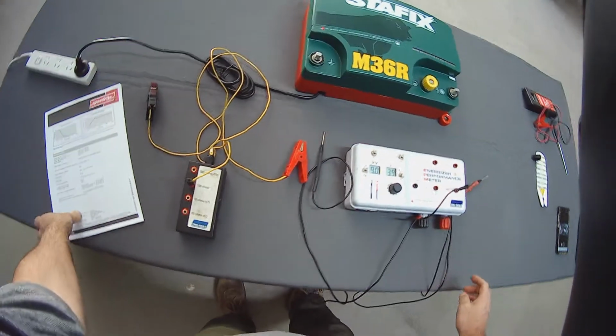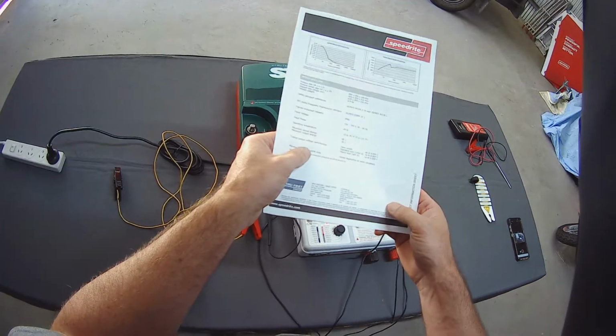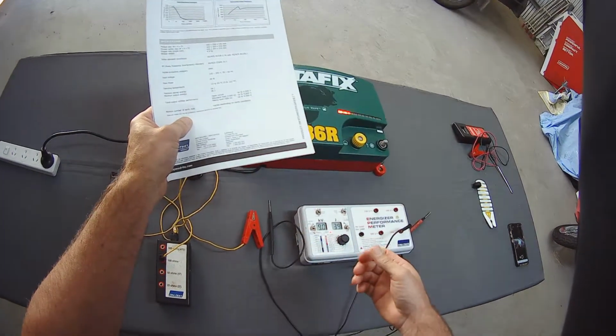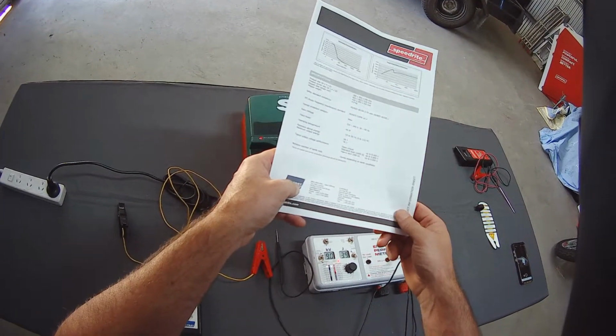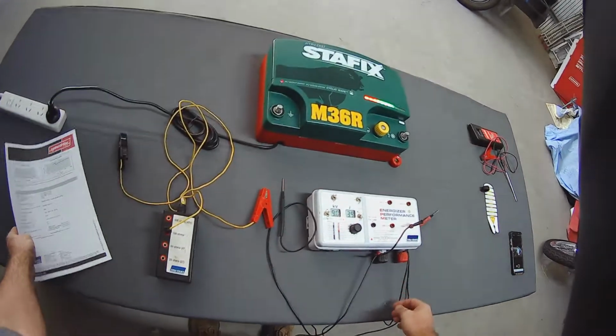So if you compare that to our output guide, a standard load, 1000 ohms, should be 8.8 kilovolts. We've got 9, so we're around the mark. Open circuit should be 9.5. We were at just over about 9. So yeah, within the ranges.